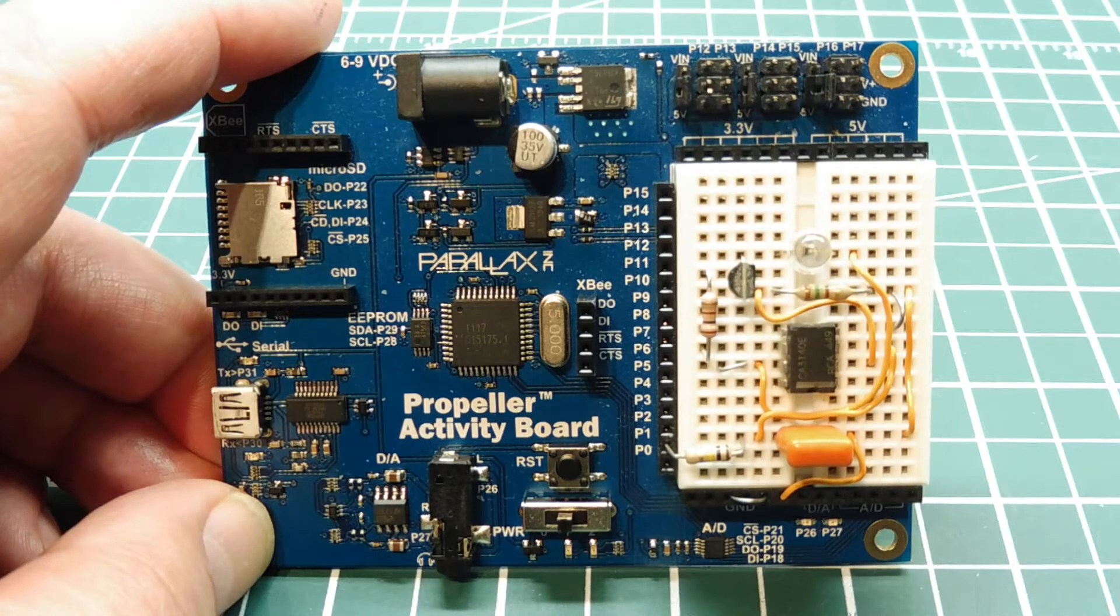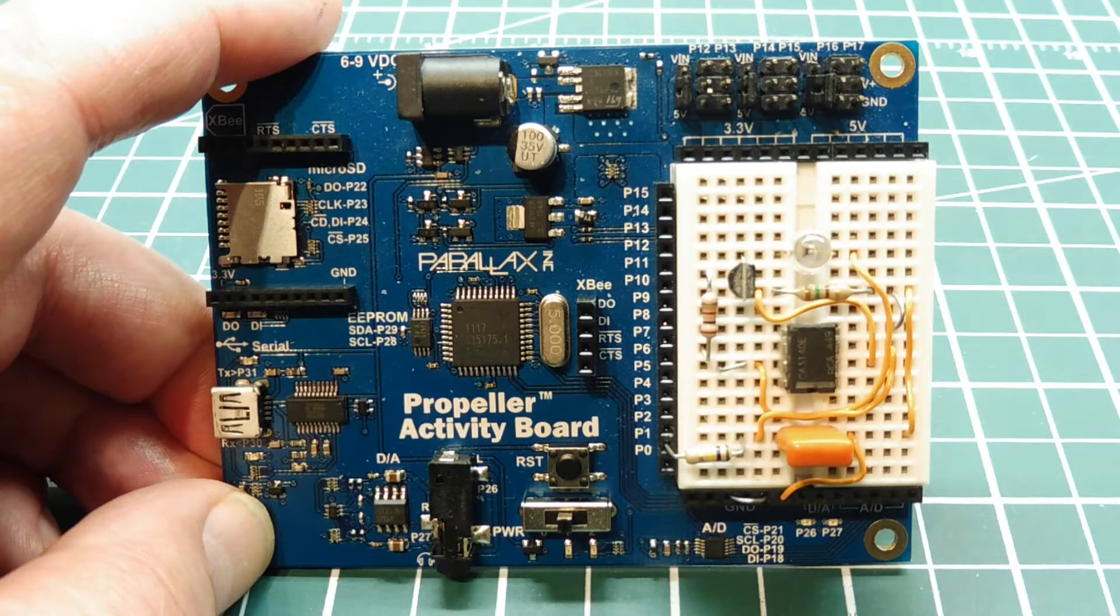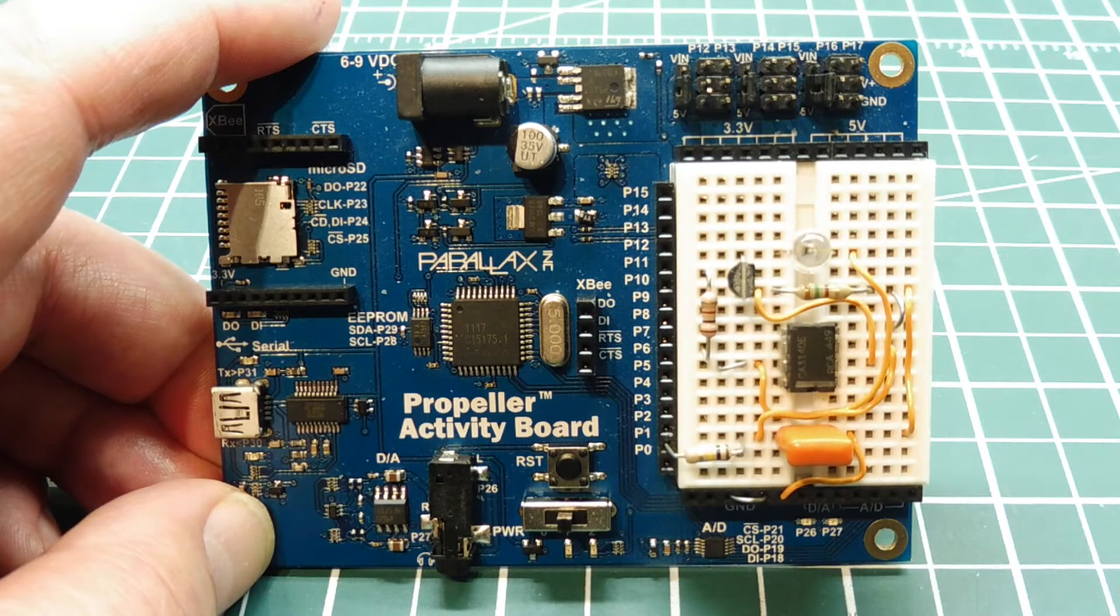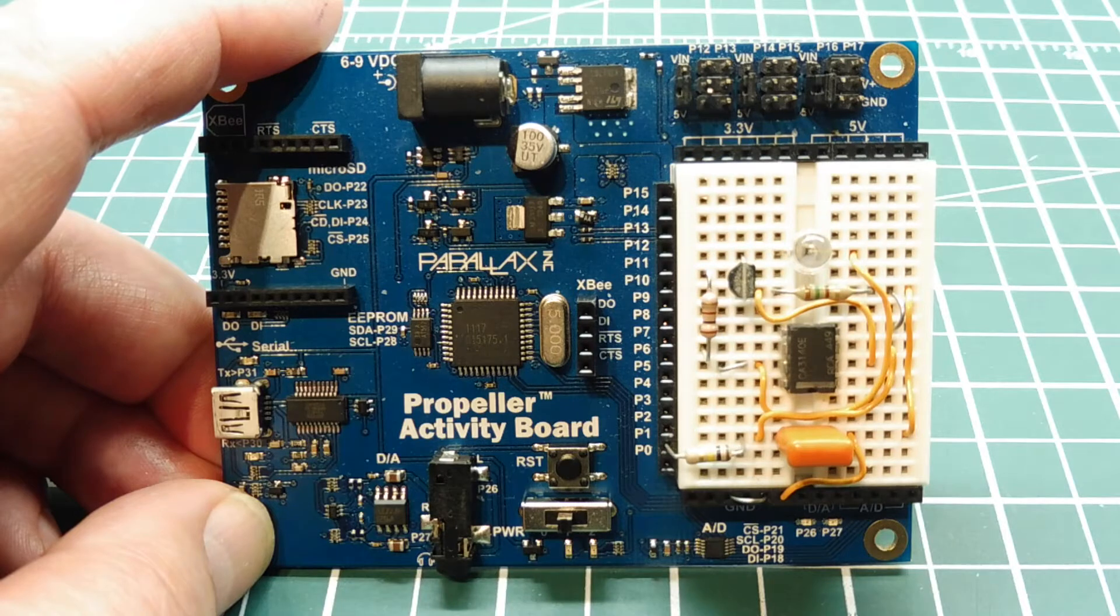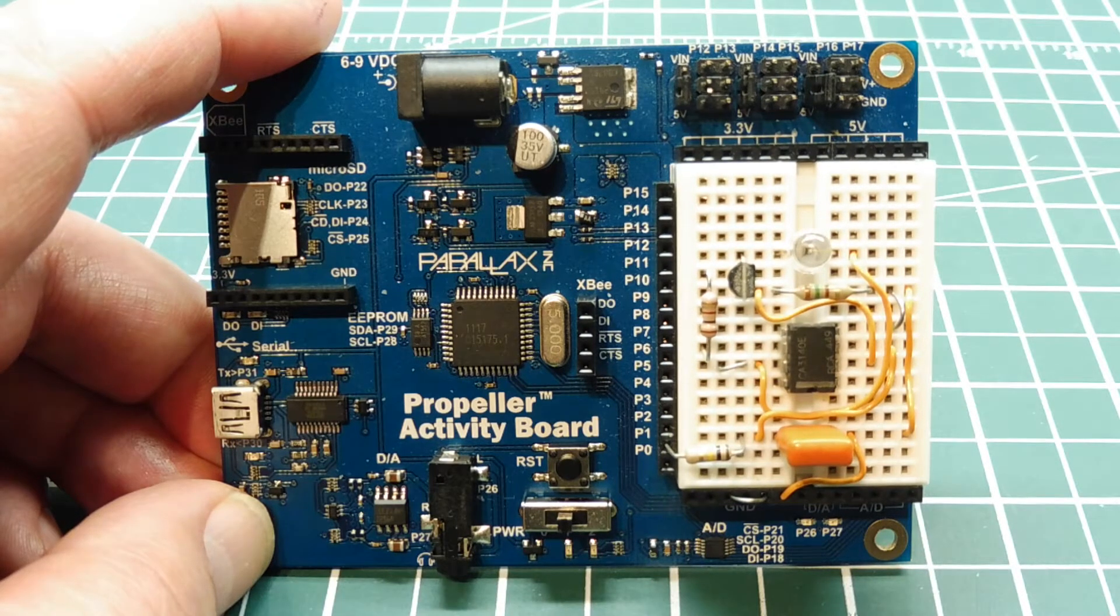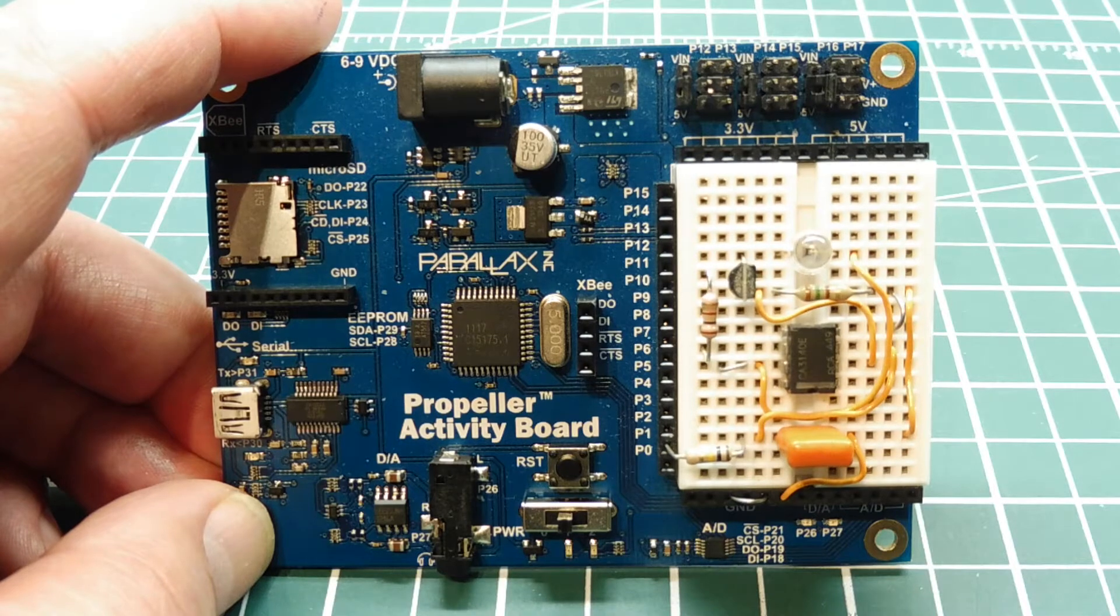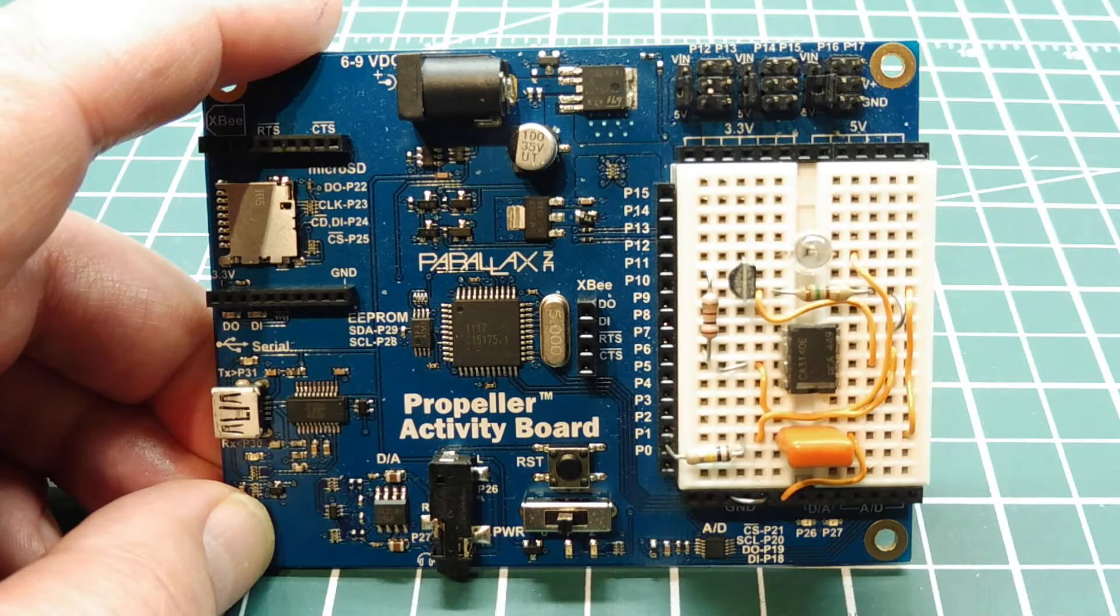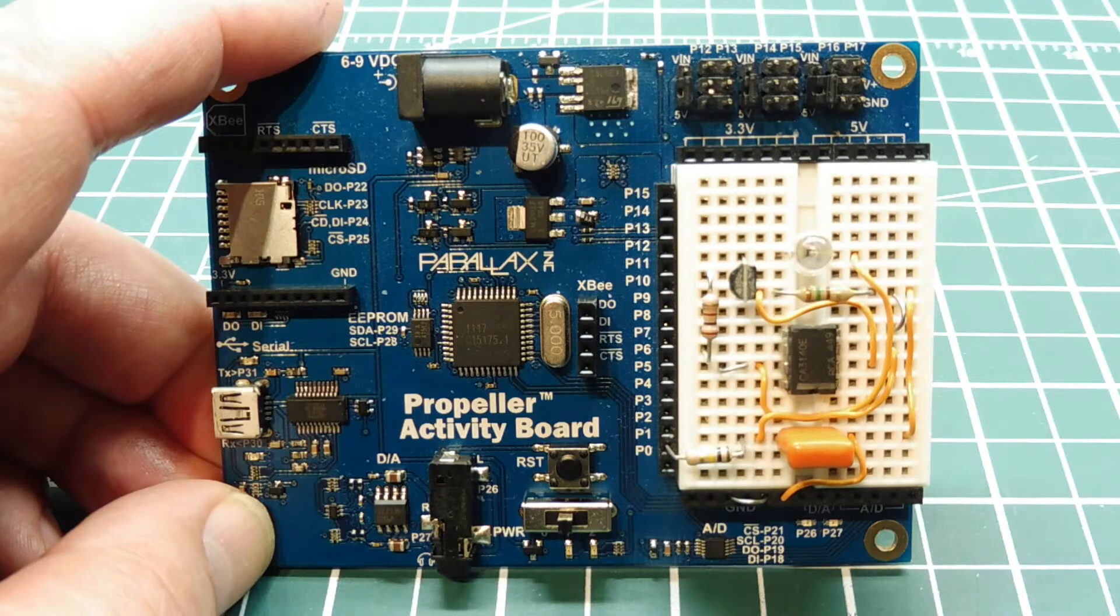Now there's another standard, it's called 4 to 20 milliamps, so instead of starting at 0, we're going to start at 4. So a couple of reasons for that. First of all, there's always current in our loop, so we can power remote devices, and it's great for troubleshooting. So we know there's always current in the loop, so if we put our ammeter in any of our loops and we detect current, we know our loop is intact.